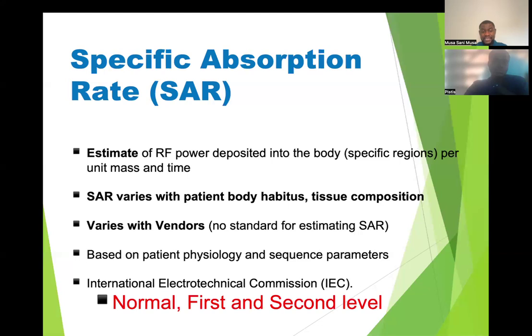So usually, like I said, we've got normal SAR mode, first level and second level. Do you scan all your patients in normal SAR mode, or first level mode, or second level mode? It's really important to scan your patient within normal SAR mode. Some patients with overheating problems, or pregnant patients, or patients with implants, you have to be really careful scanning them at first level, because what you're trying to avoid now is overheating the patient.